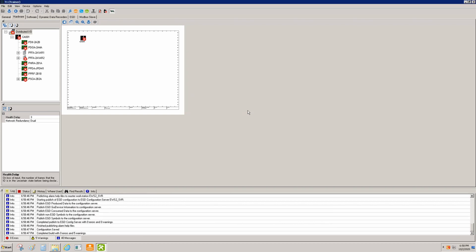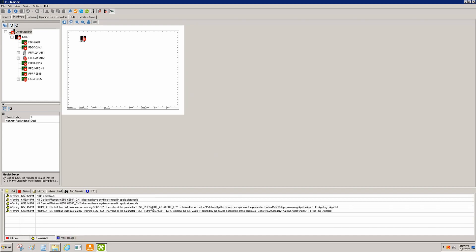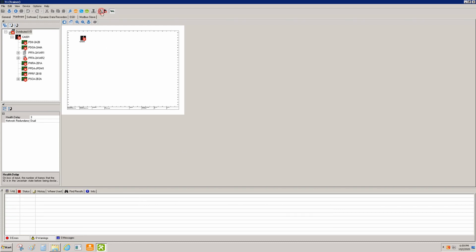Either way, if we revert we're going to have to reboot the controller, so we have to make sure we're in a safe state with the equipment in the plant. In this case it's just the controller, and this would basically be when we're doing early versions of the software or first bringing up the panel — it's probably not something you'd do to an operating plant, but it could happen. Now we've done our build, we'll check our warnings and go ahead and download.